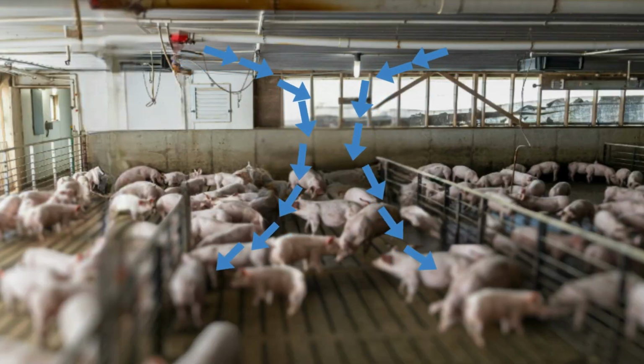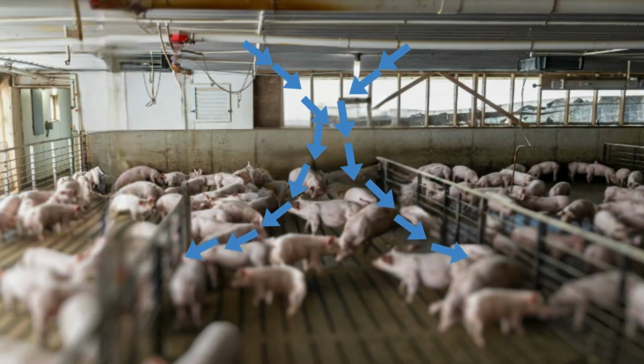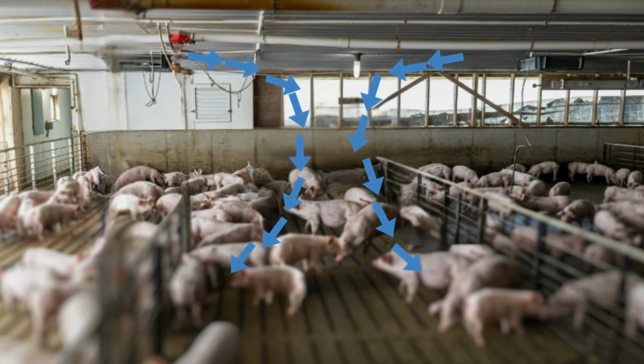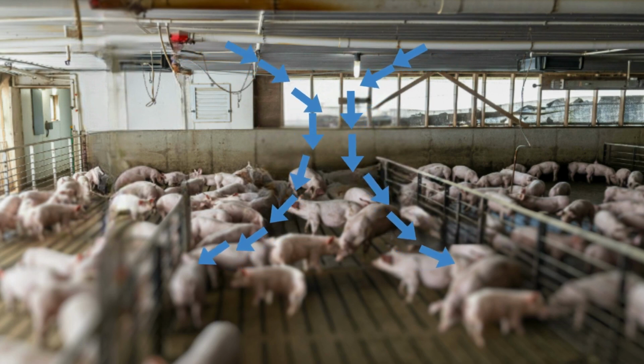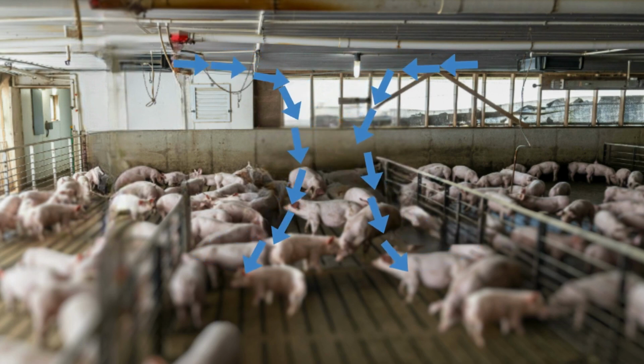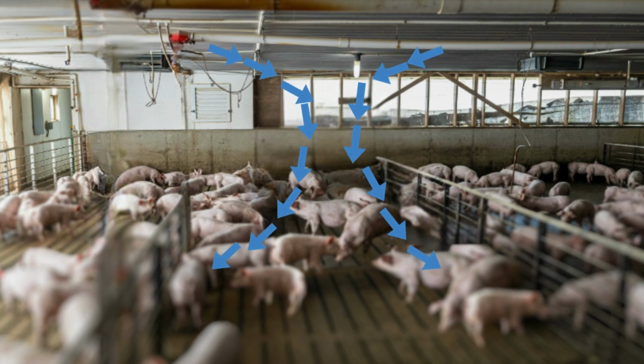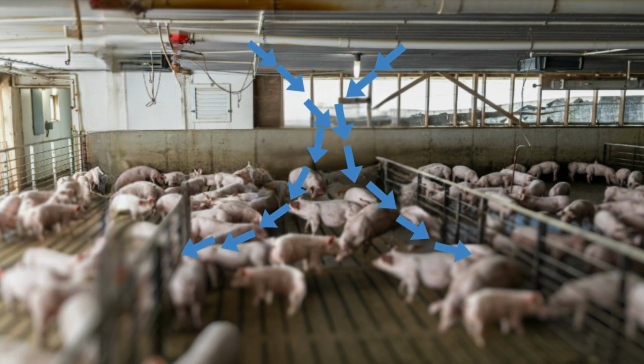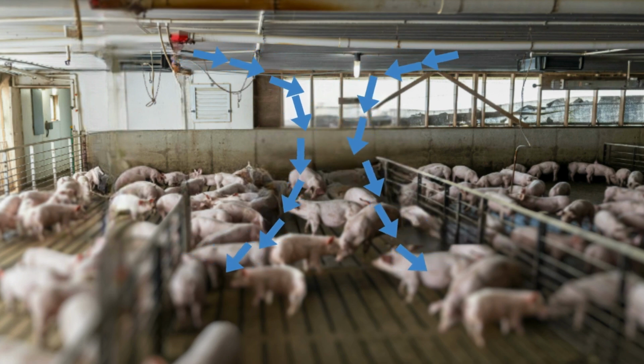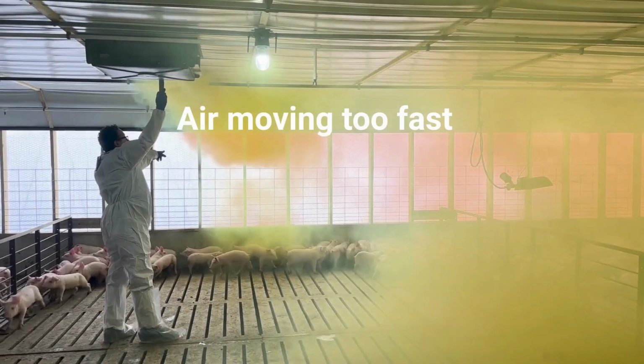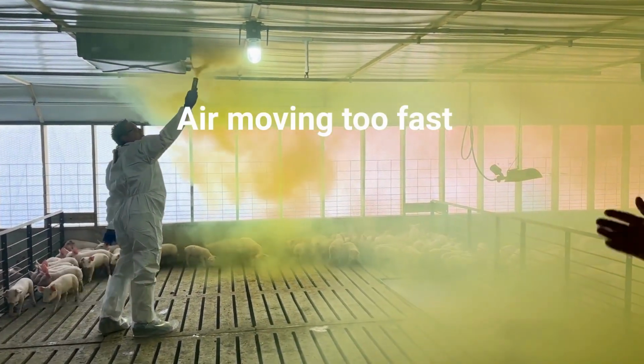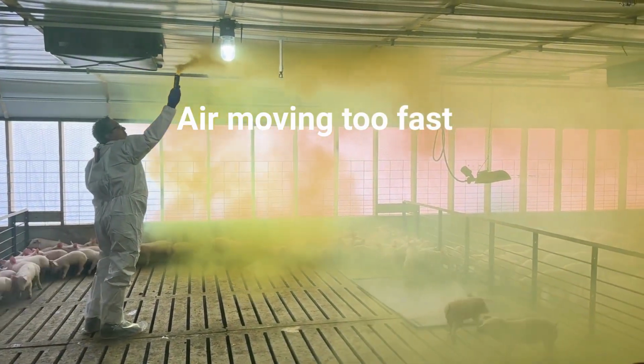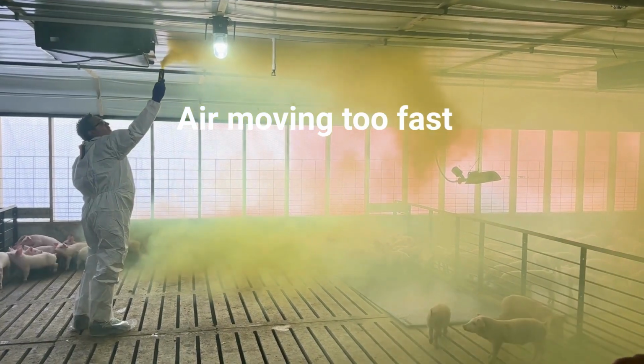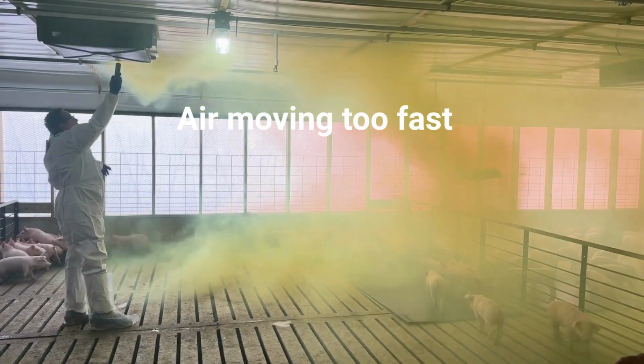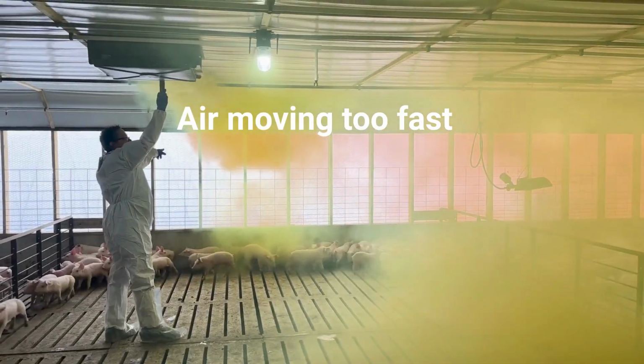Lastly, when air moves too fast, it is thrown too far. This causes it to bounce off obstacles or other airflow from adjacent inlets, overall losing control of air movement. High air speeds can also lead to chilling pigs and lack of mixing air, leading to poorly ventilated pockets throughout the room. Notice as air moves quickly out of the inlet, it's colliding with the airstream from the opposite inlet. This causes the fans to lose control over the air and forces it to drop to pig level, leading to poorly ventilated pockets.